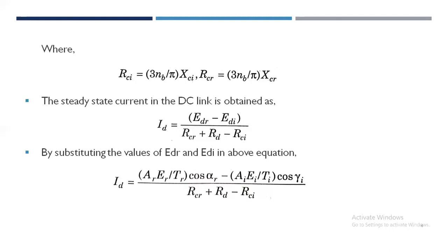Under normal conditions, the rectifier operates at constant current, that is CC control, and the inverter at constant extinction angle control. Under conditions of reduced AC voltage at the rectifier, it is necessary to shift the current control to the inverter to avoid a rundown of the DC link when rectifier control hits the minimum alpha limit.